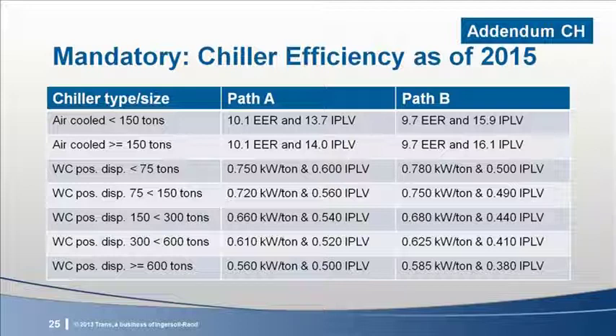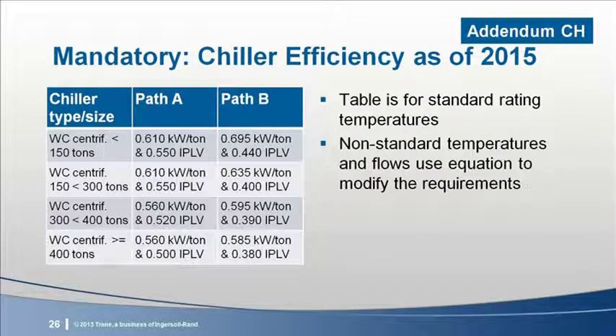As you'll see by comparing this slide to the next slide, positive displacement requirements are closing the gap with centrifugal chillers. In fact, the Path A IPLV for a 150 to 299 ton positive displacement chiller is actually more stringent than an equal capacity centrifugal chiller, but the full load requirement is less stringent. Large centrifugals were upgraded modestly, but there are some notable changes. Here you see that I've dropped the category for 600 and greater tons. That's because starting in 2015, the largest category of centrifugal chiller has been lowered to 400 tons. The rows in 2015 for 300 to 400 and for 400 and greater will be identical. It's encouraging that the best efficiency requirement for centrifugals starts to take effect at a lower capacity threshold.